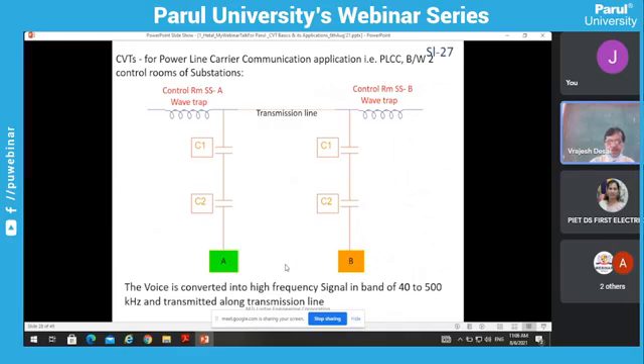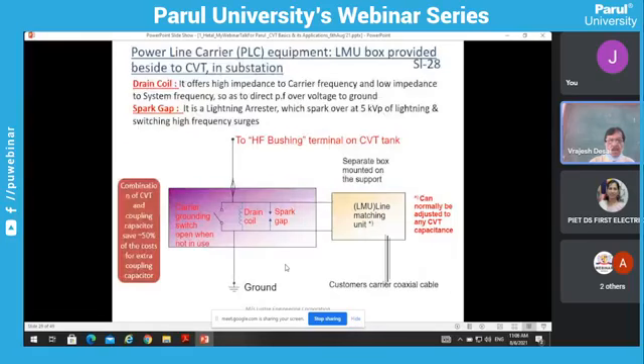So this is a very useful device, this communicating device, which is known as the power line carrier, the PLC device, which is connected like this. As I told you, there is a last point of the capacitor, that is C1 or C2, that is taken out over the tank, and before it is connected over, this PLC device is connected to it. Now this PLC device is located in the substation itself.